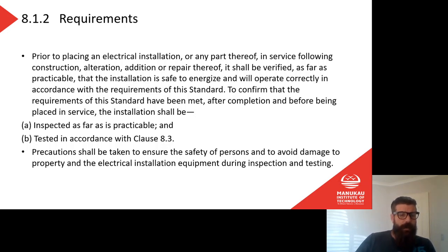So section 8.1.2 says, prior to placing an electrical installation or any part thereof in service following construction, alteration, addition or repair thereof, it shall be verified as far as practicable that the installation is safe to energize and will operate correctly in accordance with the requirements of the standard. Whew. A lot of words, and all it's saying really is once we've finished building something or altering it, changing it, whatever, so if I put in a new circuit or I build a new installation, this is saying that after I've done that work, I have to test it to make sure that it's safe. Pretty simple.